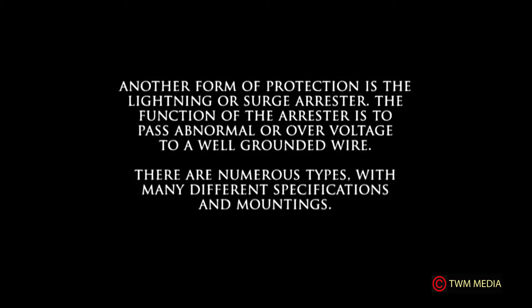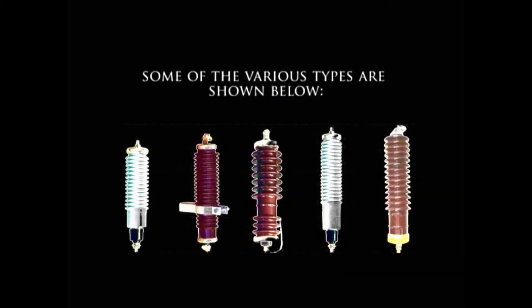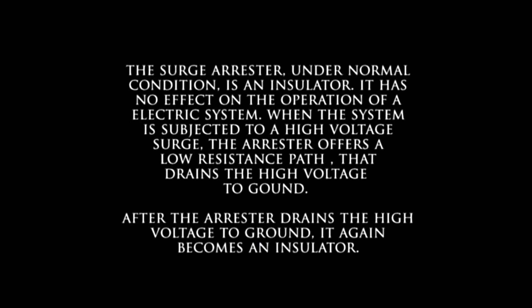Another form of protection is the lightning arrestor. The function of the arrestor is to pass abnormal or over-voltages to a well-grounded wire. There are numerous types with many different specifications and mountings. Here we see various lightning and surge protectors in a small electric substation. The surge arrestor, under normal conditions, is an insulator and has no effect on the operation of an electric system. When the system is subjected to a high voltage surge, the arrestor offers a low resistance path that drains the high voltage to ground. After draining the high voltage to ground, it again becomes an insulator.